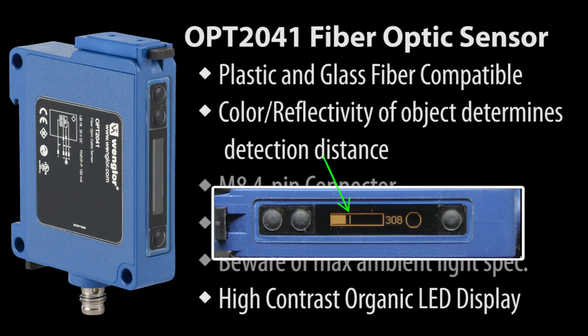This line on the bar graph is the detection threshold. Objects reflecting more light than that will be detected. The width of that line is the width of the hysteresis. You can also see a numeric version of the signal strength and the output status.